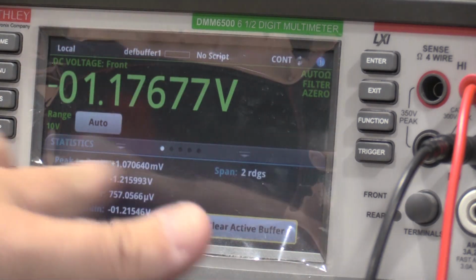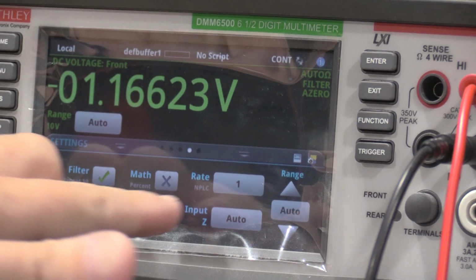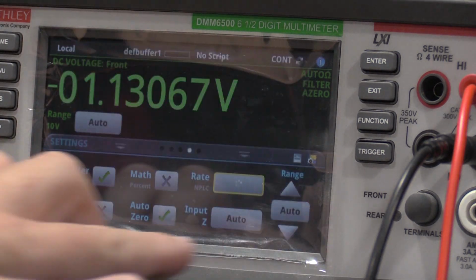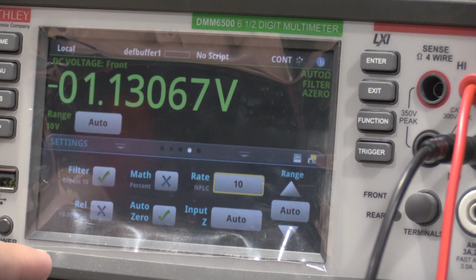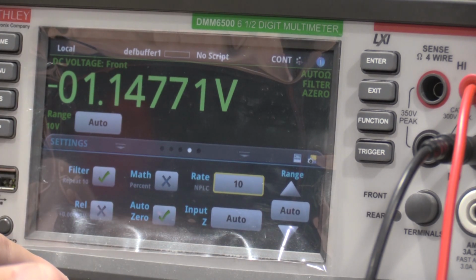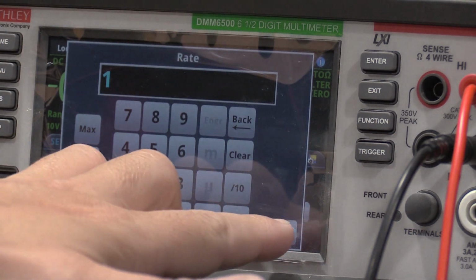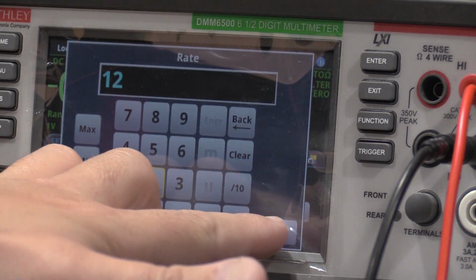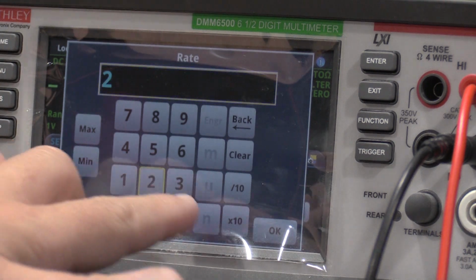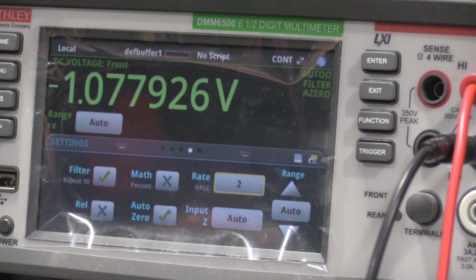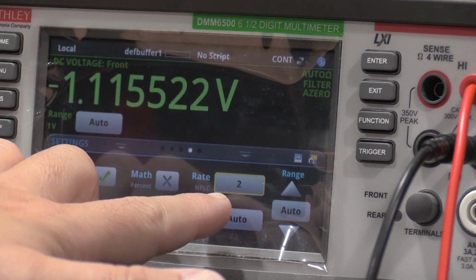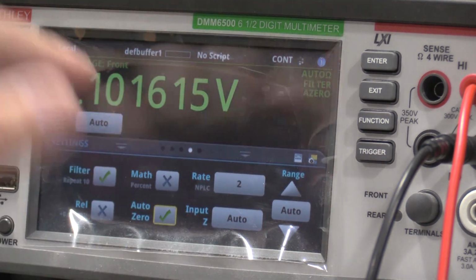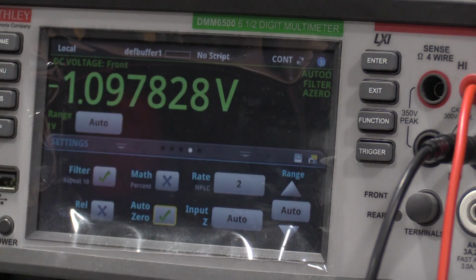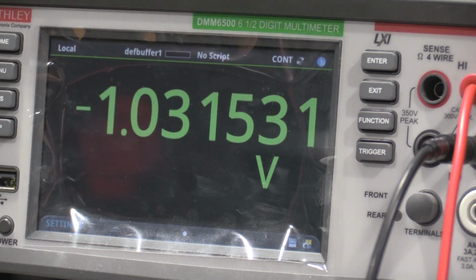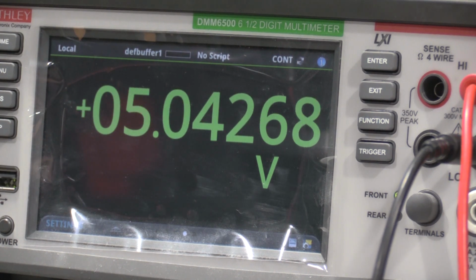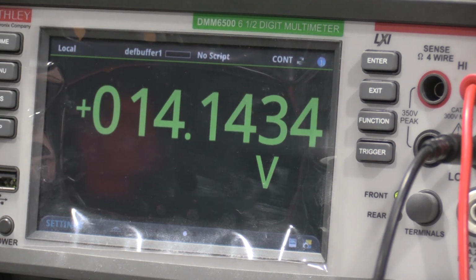And we'll clear the active buffer. Not that that matters. We'll do 10 power line cycles with filtering. Two power line cycles with filtering, let it update a little quicker. I have filter on, so it's taking a reading every 2 power line cycles, but then it's doing 10 readings as it's going through. So for this, we'll blow the display up, and this will be +15.